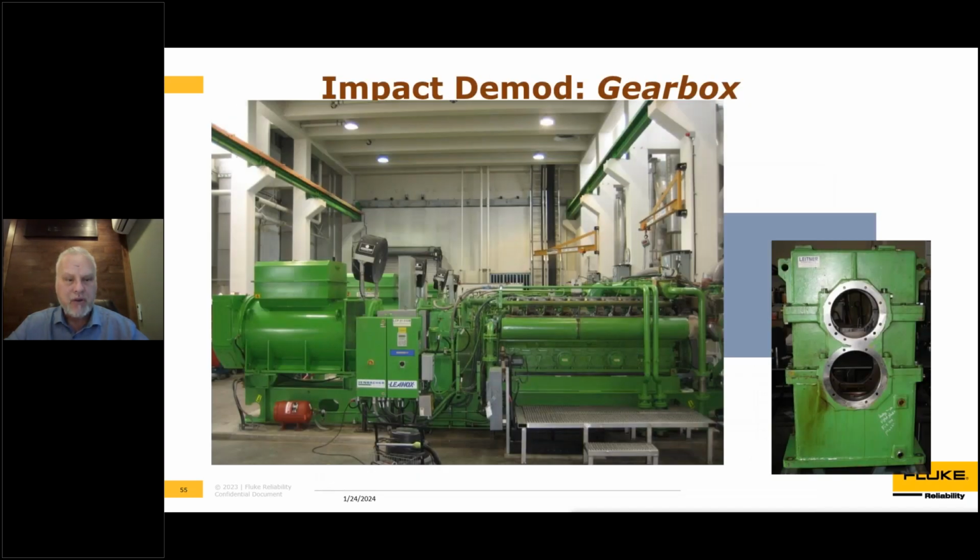I'm going to give you another interesting example because this particular one is, I'd say, a diesel engine. It's a combined fuel type engine that was running through a gearbox, through a speed-up gearbox, to a generator. And surprising enough, we can and have successfully used this tool in certain diesel diagnostics. Again, diesels come with their own amount of built-in impacting, different discussion, but it does prove that the tool can be effective in that scenario.